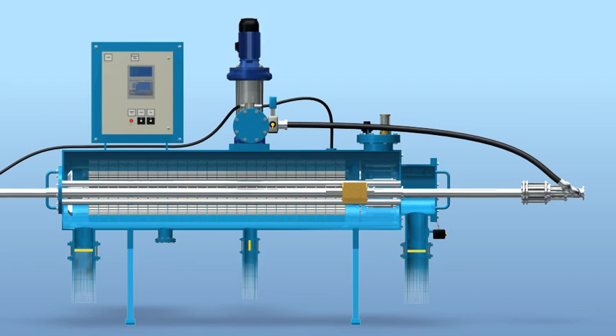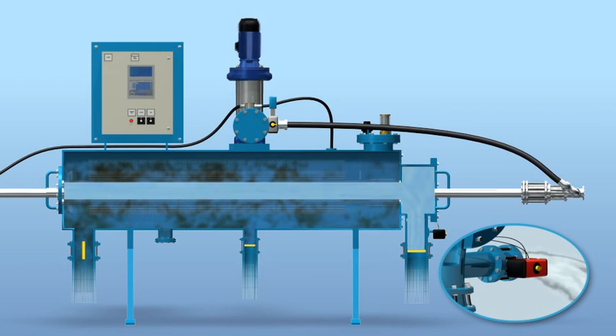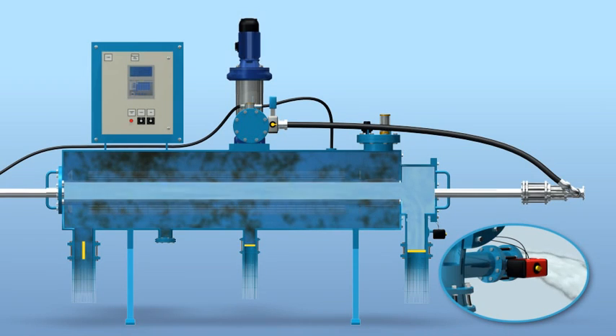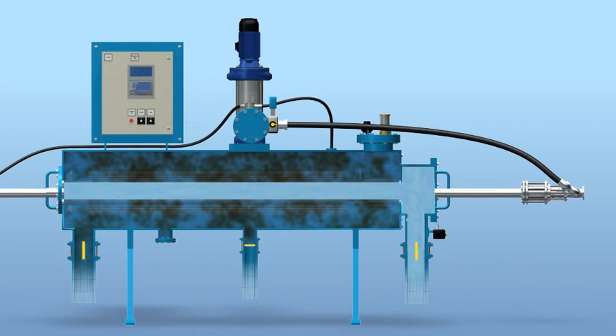Once the spray cleaning of all the cassettes is completed, the flushing and the drain control valves are closed, and the inlet and the filter to waste control valves are opened. Raw liquid enters the filter and fills it up. Air is displaced via the air release valve, and initial filtrate is passed through the filter to waste control valve. The filter to waste control valve closes, followed by the outlet control valve opening.